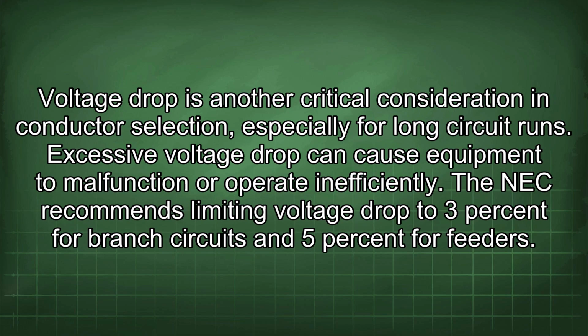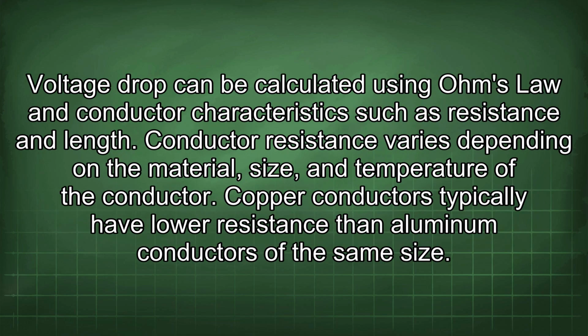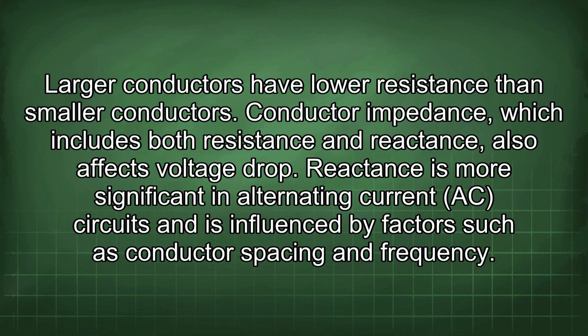The NEC recommends limiting voltage drop to 3% for branch circuits and 5% for feeders. Voltage drop can be calculated using Ohm's law and conductor characteristics such as resistance and length. Conductor resistance varies depending on the material, size, and temperature of the conductor. Copper conductors typically have lower resistance than aluminum conductors of the same size. Larger conductors have lower resistance than smaller conductors. Conductor impedance, which includes both resistance and reactance, also affects voltage drop. Reactance is more significant in alternating current (AC) circuits and is influenced by factors such as conductor spacing and frequency.